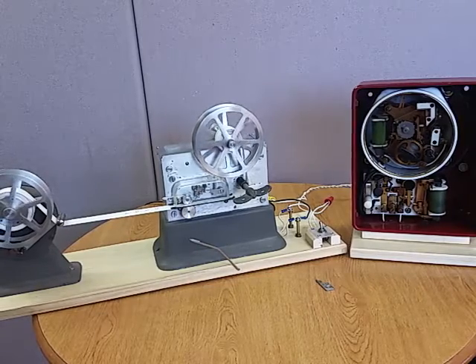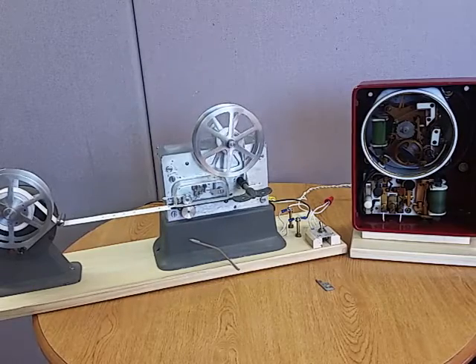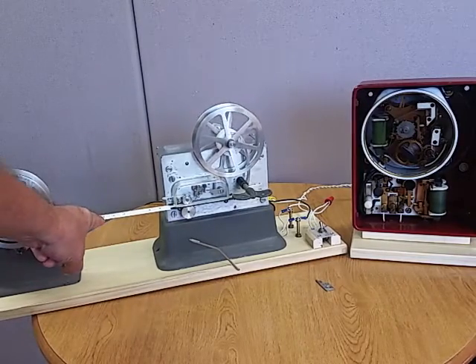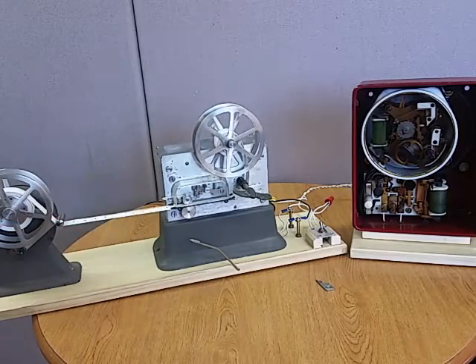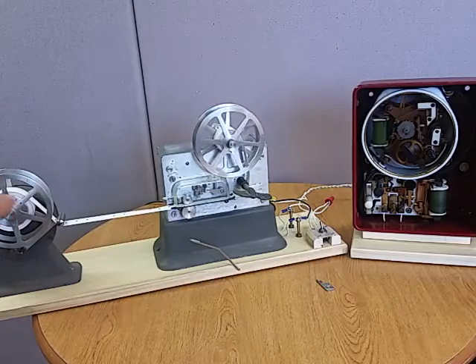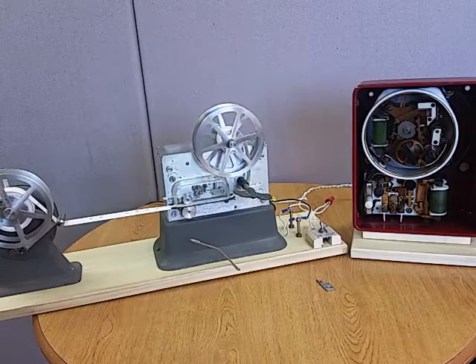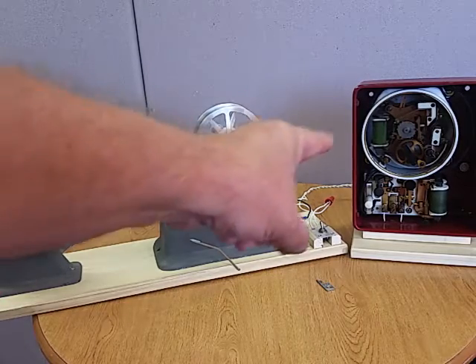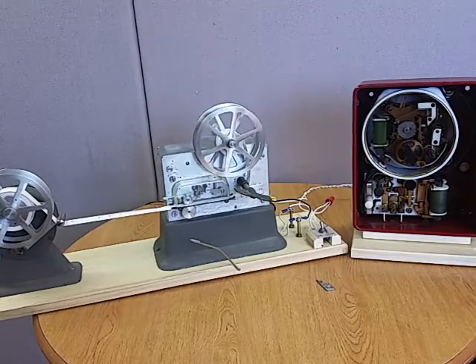It will run 4 cycles of the code, so it'll send out 424. You can see it running here — there's 4, there's 2, and 4 is coming up. When the fire station receives this alarm, they'll see the 424. They'll look it up on their master list and they'll know where the call is coming from. It's an ingenious system.